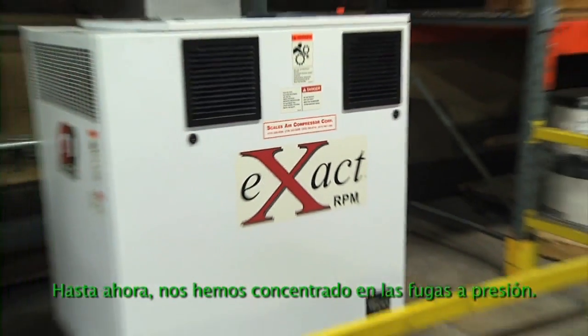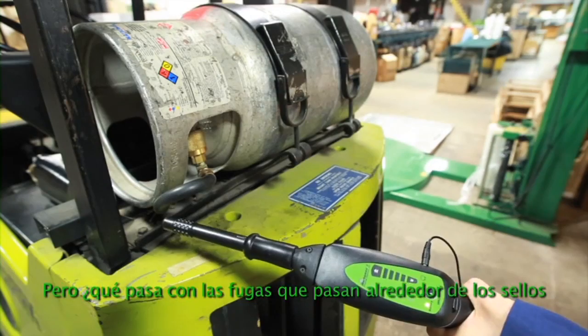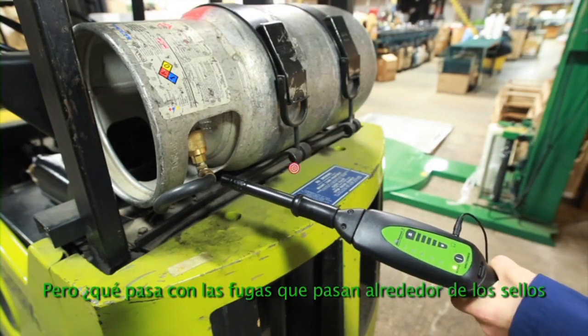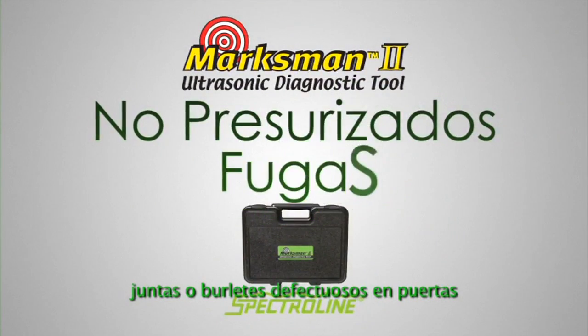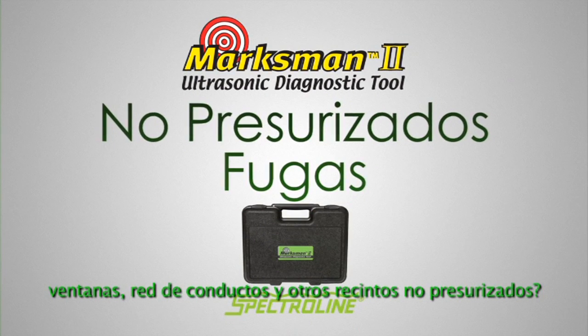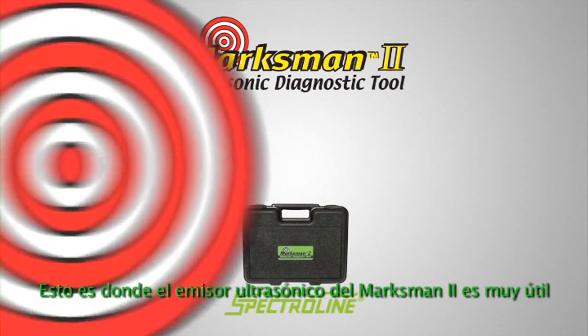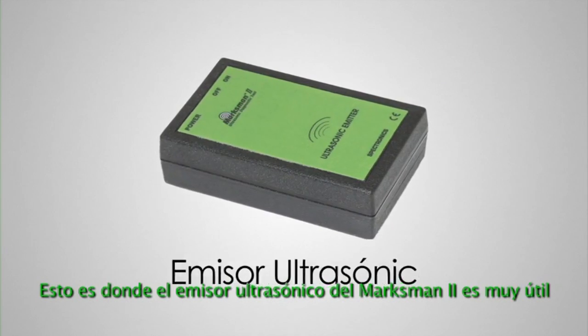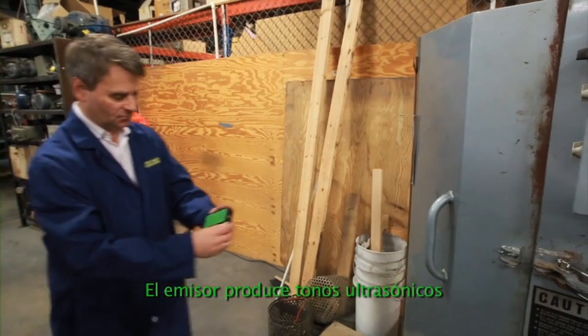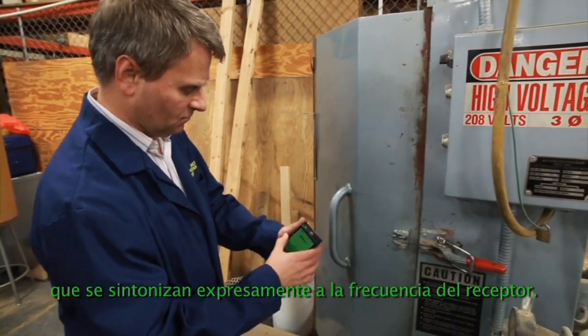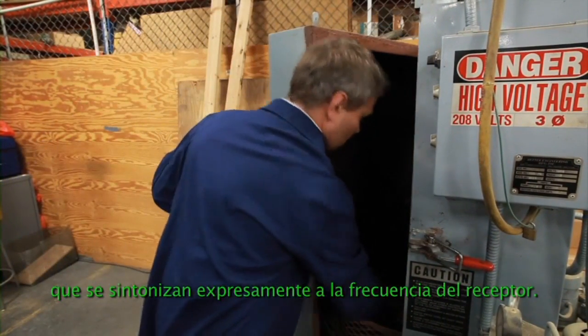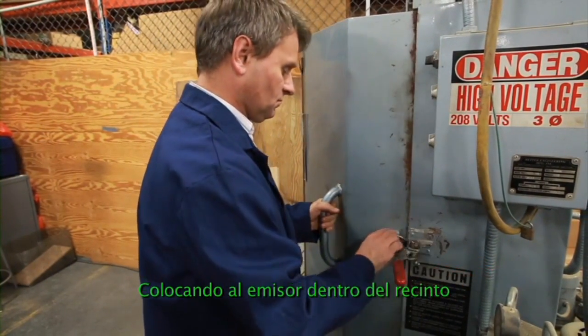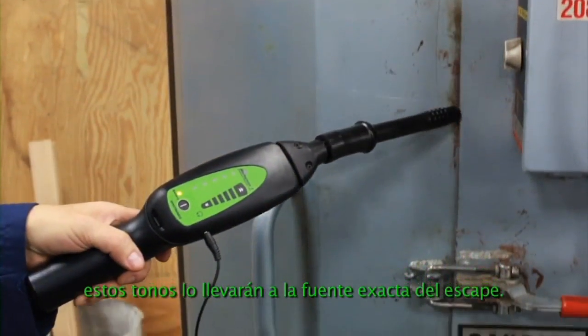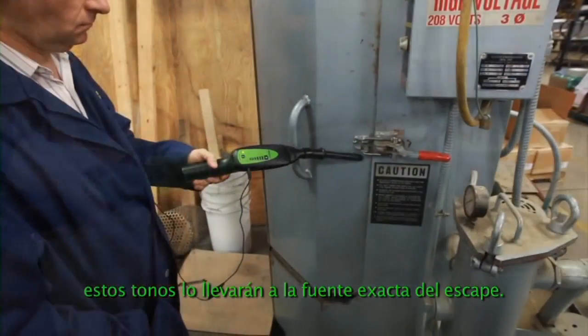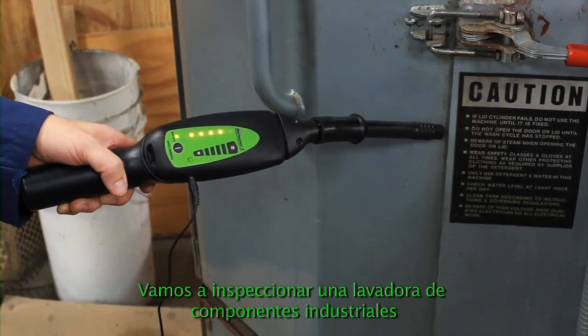So far, we've focused on pressurized leaks. But what about leaks that pass around faulty seals, gaskets, or weather stripping in doors, windows, ductwork, and other non-pressurized enclosures? That's where the Marksman II's ultrasonic emitter comes in. The emitter produces ultrasonic beeps that are tuned specifically to the frequency of the receiver. By placing the emitter inside the enclosure, these beeps will lead to the exact source of the leakage. Let's check out a leaky parts washer and see if we can find out where the problem lies.